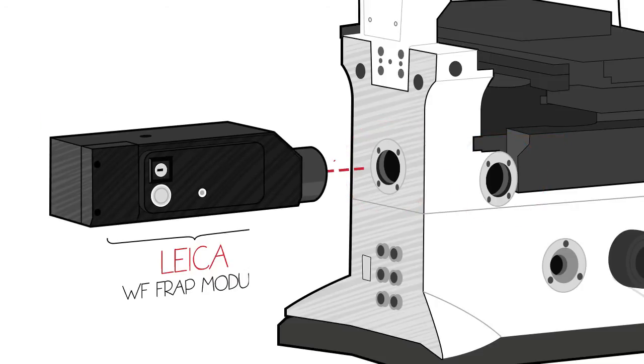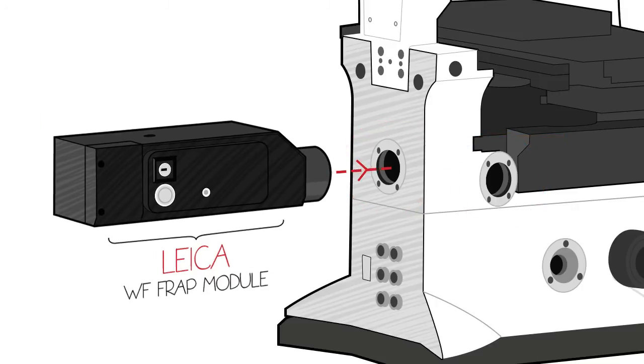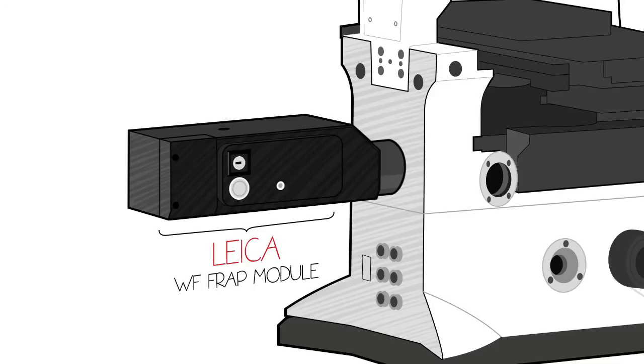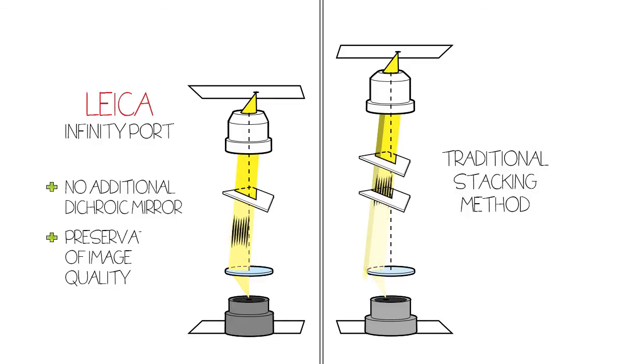The Infinity Port maintains the best optical quality by providing up to two ports with direct access to the infinity space of the microscope. This direct access does not require elongation of the light path or the addition of a dichroic. As a result, the Infinity Port provides the ability to add photomanipulation components without sacrificing the optical quality of the image.